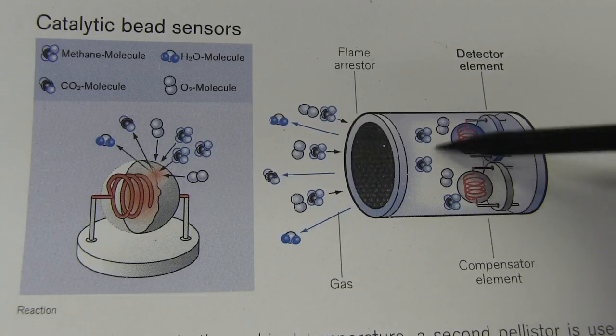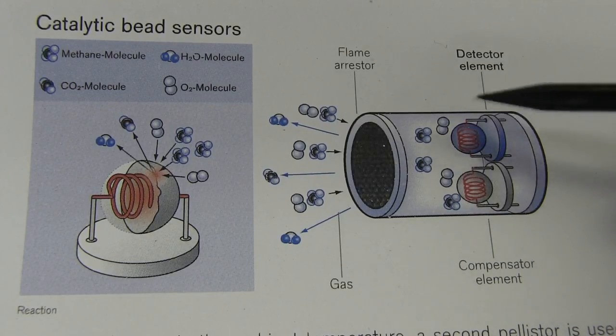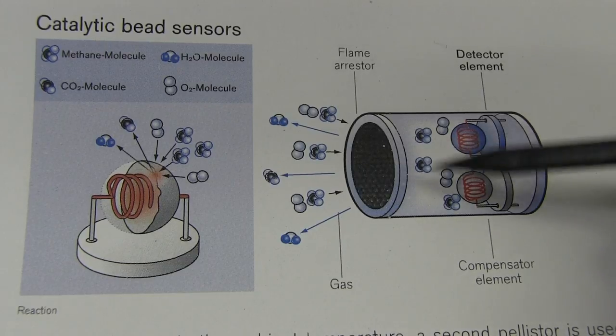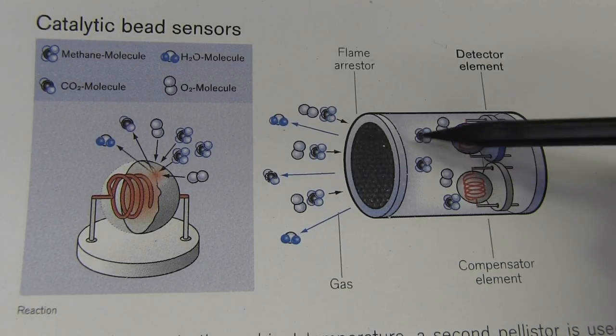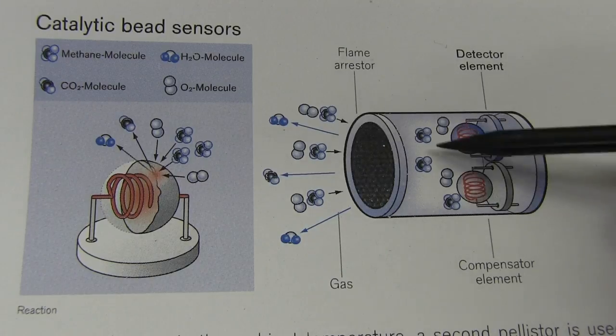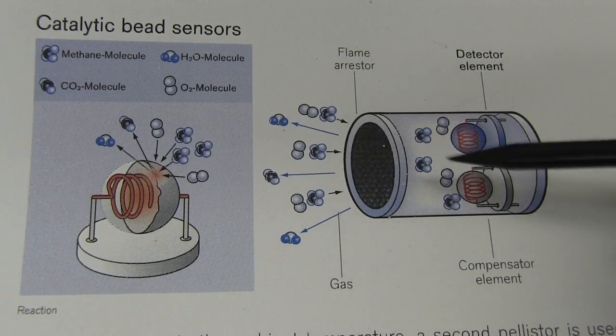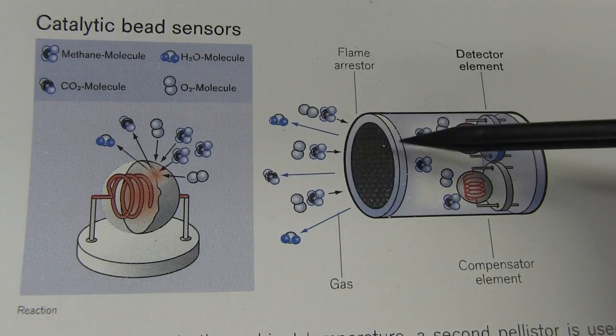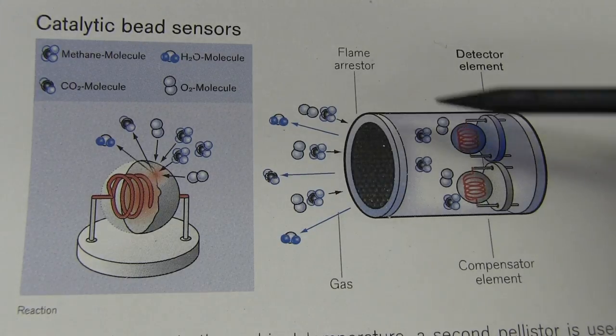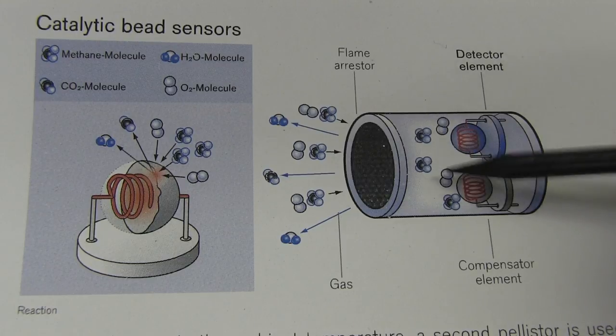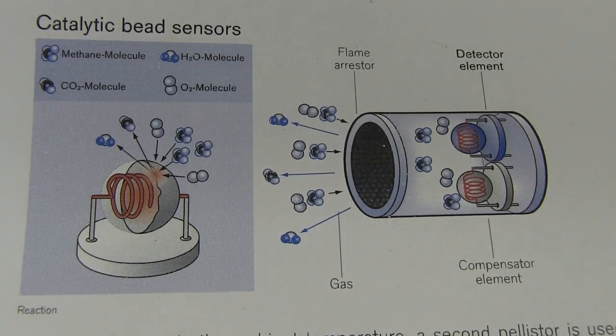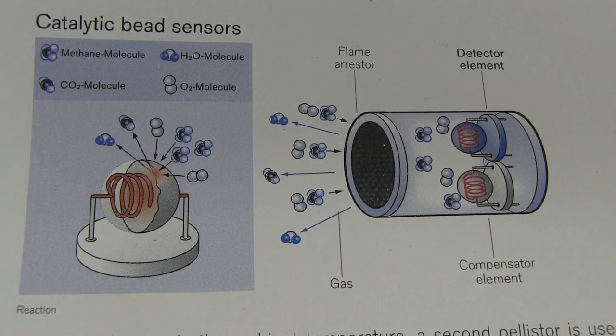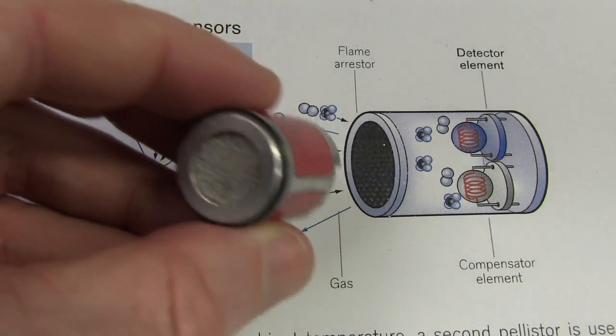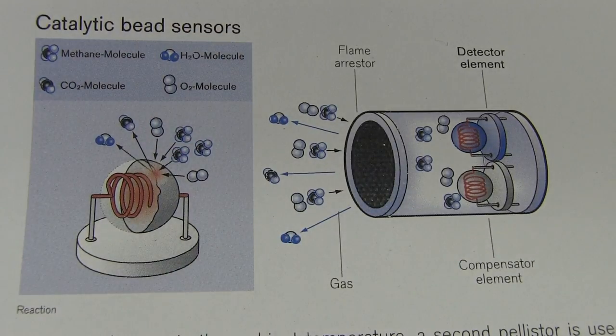Brilliant. So yes, the gas inside here can actually explode, because hey, we're trying to detect combustible gases - they're going to combust, right? To stop it, they've got this flame arrestor and a sinter disc inside, which controls the reaction. It stops it blasting out the end, but also stops the reaction internally, so if it does explode, it self-extinguishes. That's why you can use these sensors in an intrinsically safe product in a combustible environment. Yes, they do combust it, but hey, do it safe.